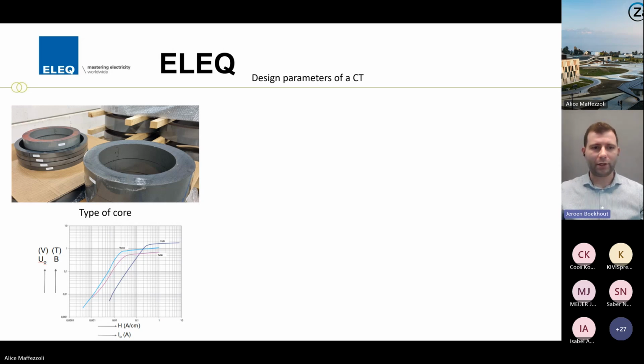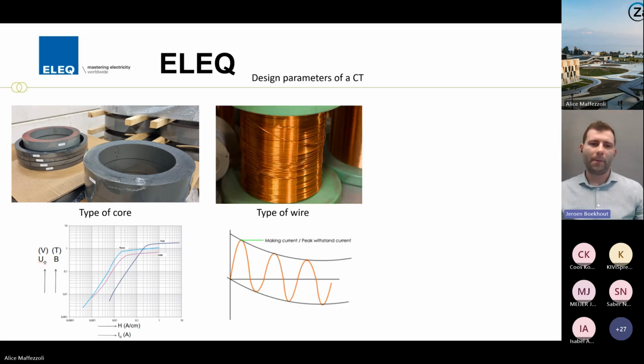Then the second part is the choice of wire. This choice is mainly based on required temperature characteristics — there's secondary current flowing, and short-time current tests and thermal overload tests where you don't want the wire to become a heat element. With an LPCT, you can control the secondary current through the combination of components, so there's a limit in heat generation, and you can also determine the burden in a sense.